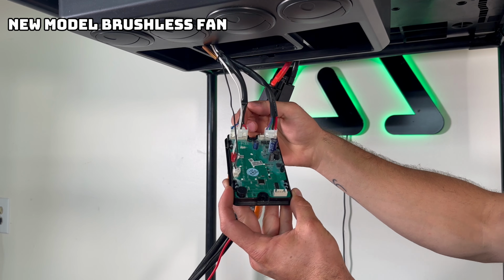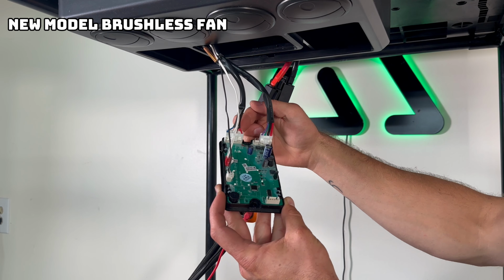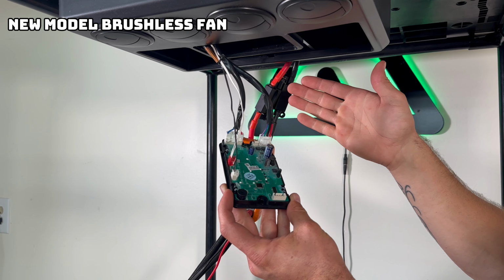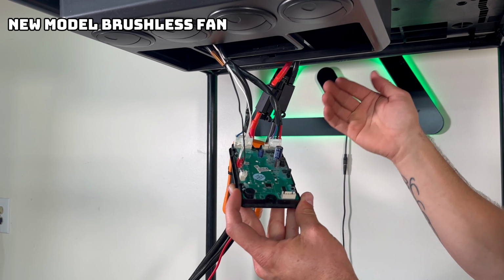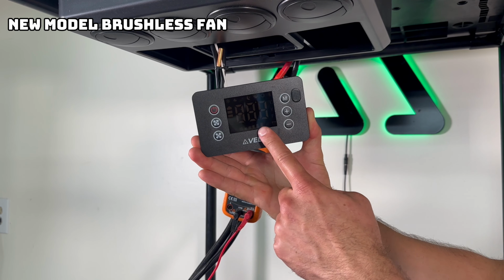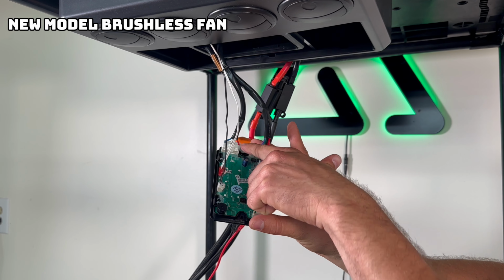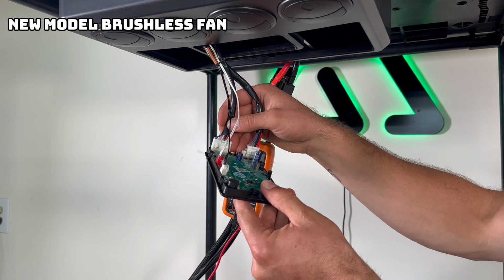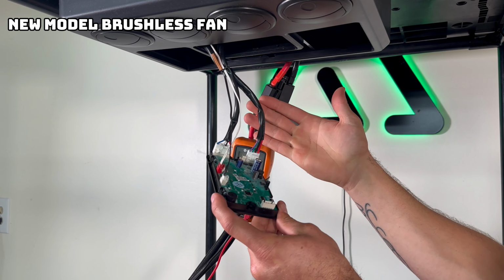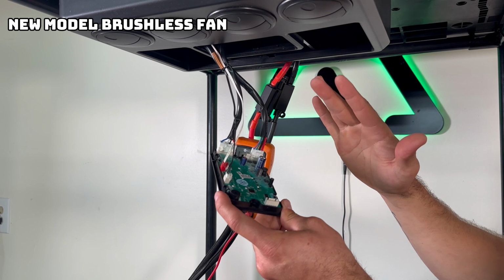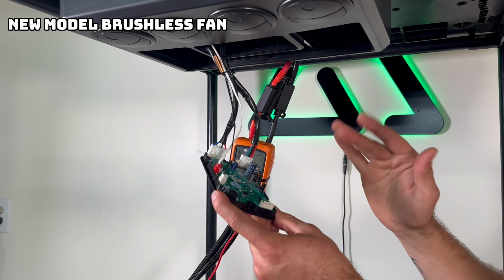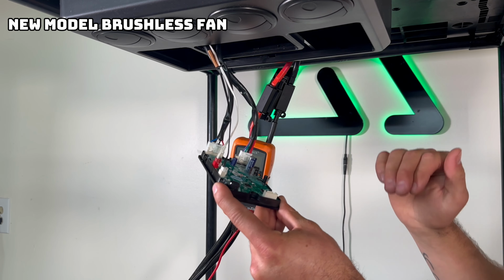So you've got a red and a black wire. This should be supplying just steady 12 volts all the time to the fan as long as there's power hooked up to the unit. It could not even be on, and there should still be voltage to these 2 pins. Then the blue and white wire are the signal wires, and this varies anywhere from 0.5 volts up to about 2 volts. That's what actually controls the speed of the fan.